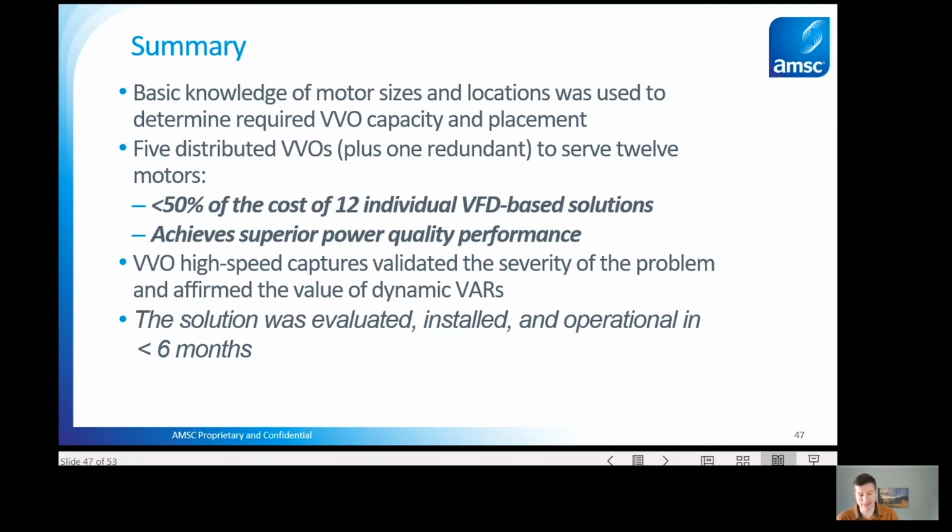This solution was less than 50% of the cost of using VFDs. So if this were to be applying VFDs, you would have had to have a VFD on every single motor, which would have been substantially more expensive, as well as more time consuming, as well as would involve altering the plant, which a lot of industrials would much rather not alter their plant. And then also achieving much superior power quality performance, because the VVOs are there specifically and only to make sure that the whole system's protected, unlike a VFD, which cannot guarantee that.